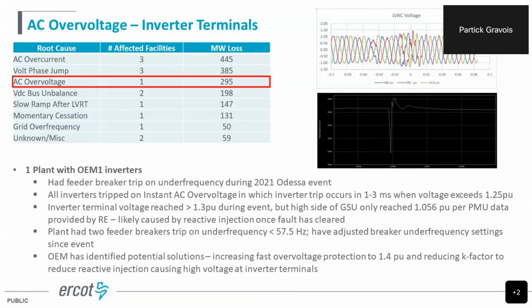So I just want to point out for all of the OEM 1 inverters, they have the overvoltage situation, they have the overcurrent, they have the volt phase jump. For all of these facilities, we are recommending that they fix all of these mitigation plans at their facility simultaneously. And that's being done at these 6 facilities. Once that's done, we're going to reach out to other facilities with these inverters to recommend they start implementing these corrective actions as well, preventively, to prevent any potential events with the other units tripping off as well.